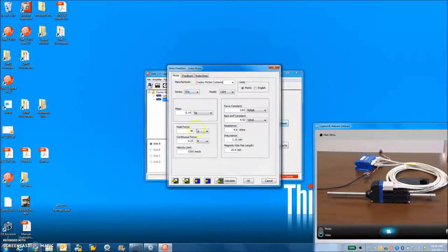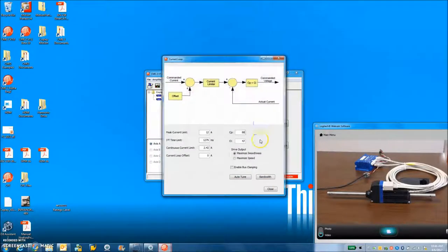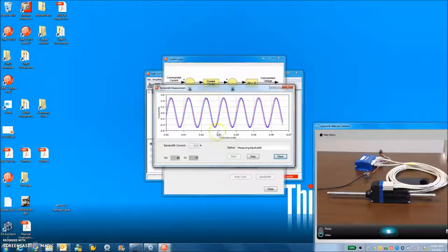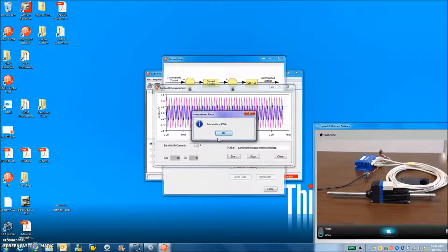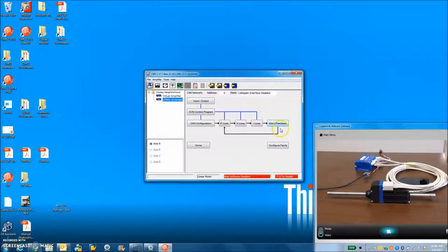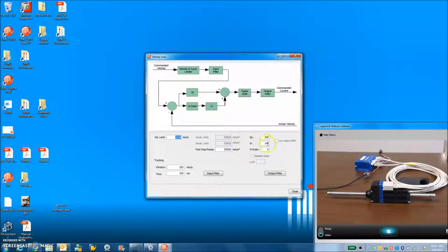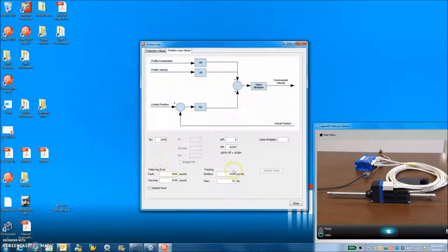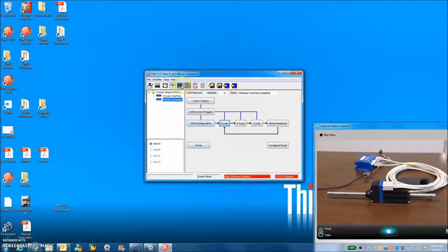That's good. We can see our motor data. That's the same. We can see the interpolation rate. I'm just going to go down the list here. Look at the current loop bandwidth. It's a linear motor. How much current loop bandwidth do you need? You're only going through so many electrical cycles per second. 400 hertz is fine. We don't want to overdo it. There's probably a 350 hertz limit anyways for the velocity loop based on the sine cosine filters. So we have to watch that. There's speed limit, some gain parameters, position loop, default parameters. That's all nice. Some trajectory limits, crazy accelerations, some pretty high speeds. We can crank that up if we want.